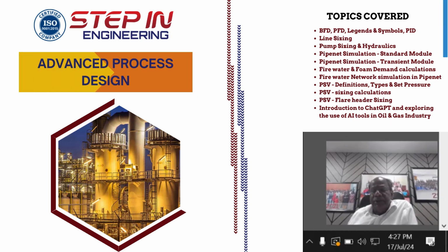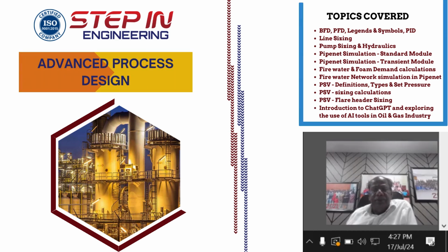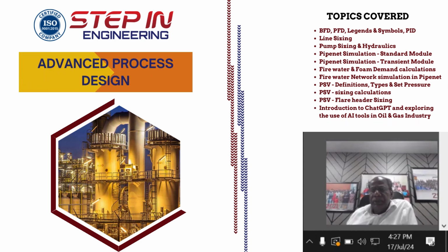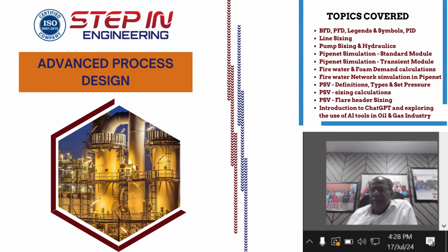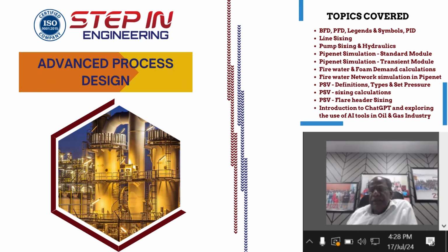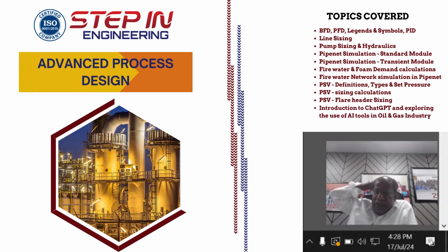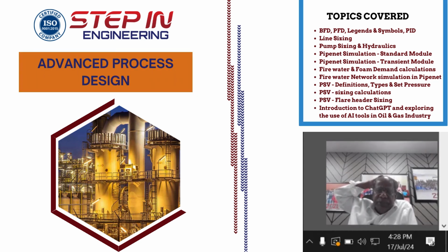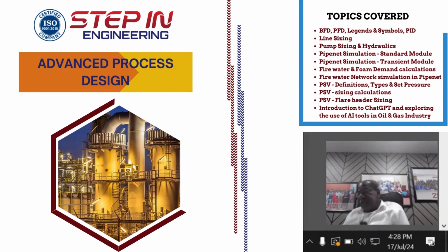These things are very important when you build a new plant. Transient analysis has to be done for each and every pump, and not only for the pump, but wherever there is a control valve, an ESD valve, or a PSV. When the ESD valve closes, it normally closes very fast, within a few seconds. What is the impact on the pump discharge? What will happen to the piping design pressure? Is the pipe designed for such a high surge pressure? These are things to be checked during the design stage. If the piping is not able to withstand it, then you have to go for a higher rating. These things will be demonstrated through the transient analysis.